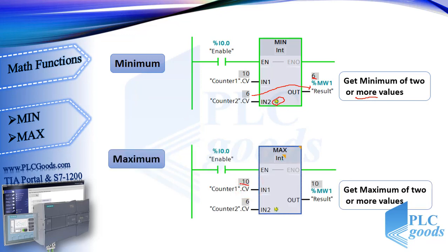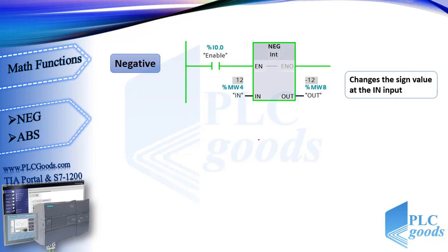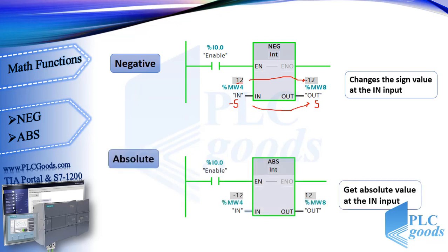The MAX function shows 10 from its inputs. The negate function changes the sign of the value at the IN input — if it is 12, this instruction will give us -12; if the input value is -5, it will send 5 to its output. ABS is the syntax for the absolute function used in many programming languages — it gets the absolute value, so for either -12 or 12 at the input, the output will be 12.